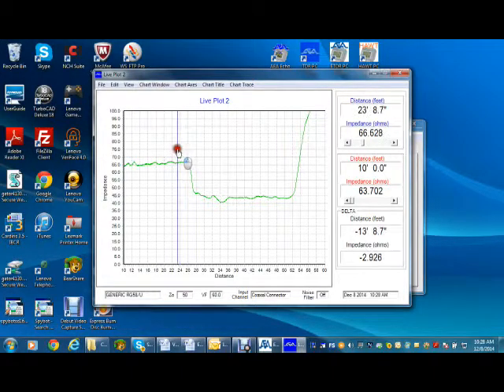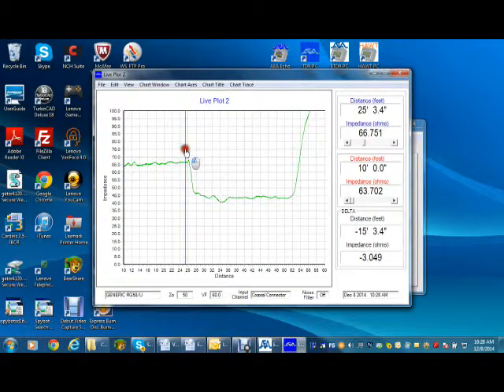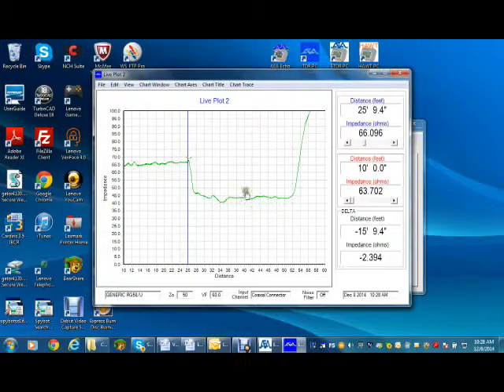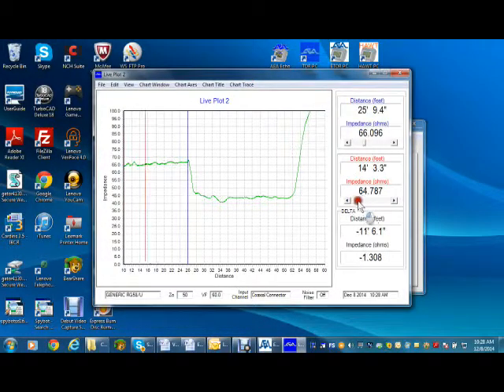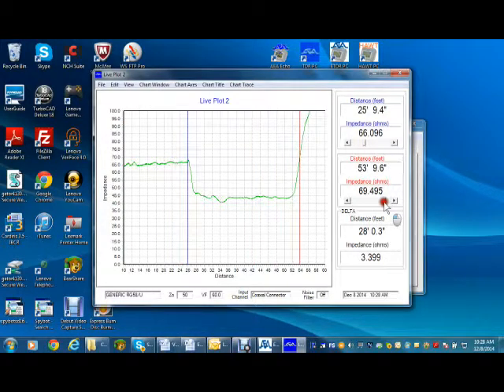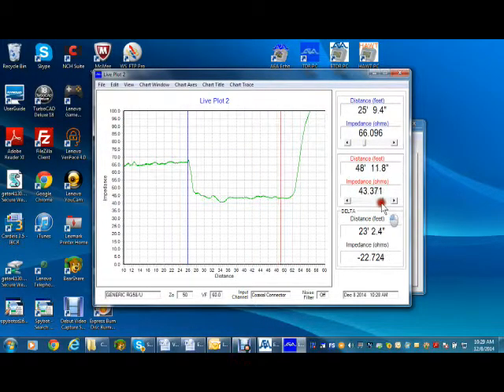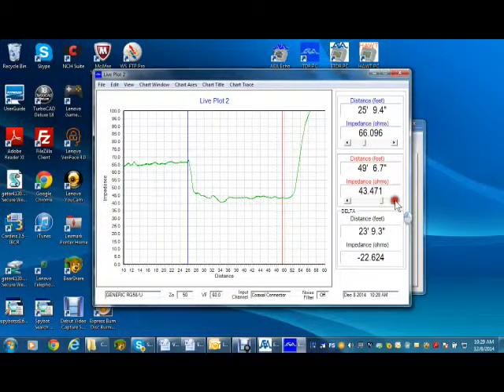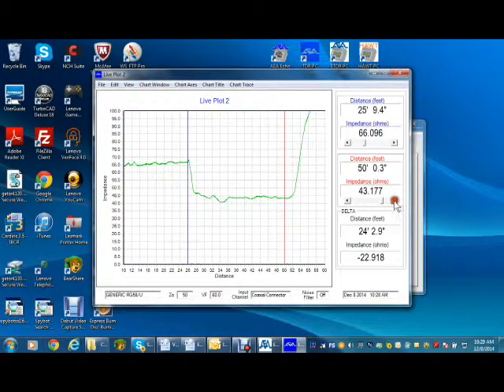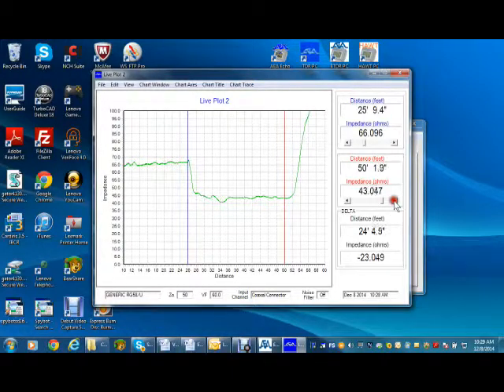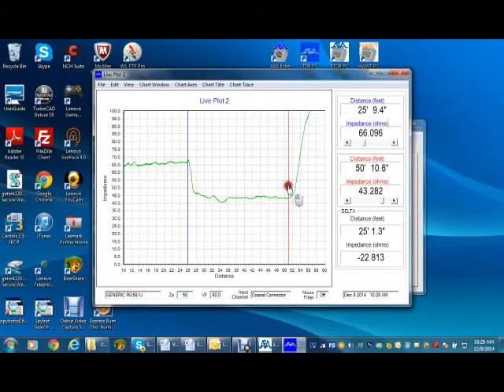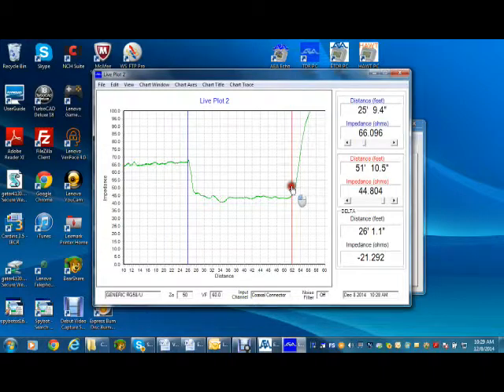The two cursors can be moved directly or by using the controls under their data. The cursor's delta is the difference in the red and blue cursor's distance and impedance readings. Delta distances may appear negative or positive depending on the red and blue cursor positions. Positive distance, as shown here, indicates moving away from the TDR, blue to red, and negative if it's back towards the TDR.